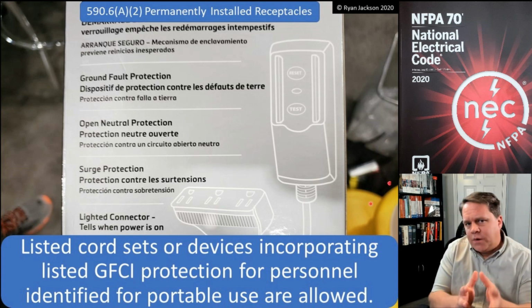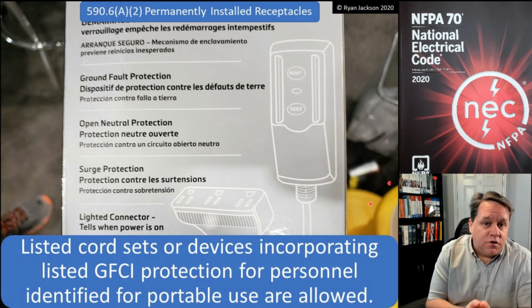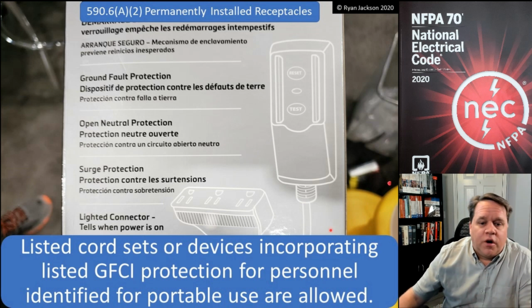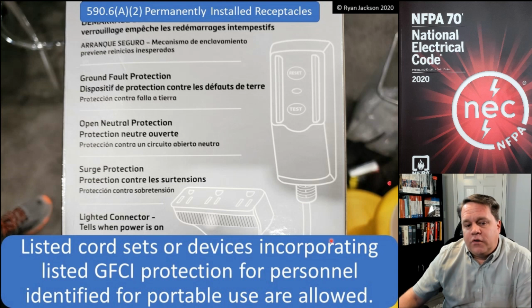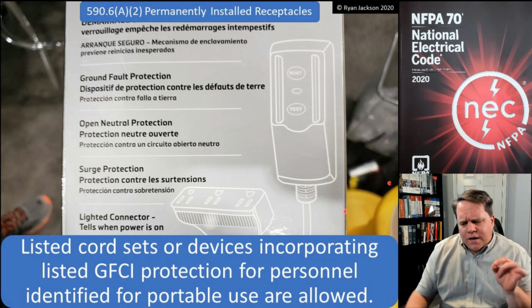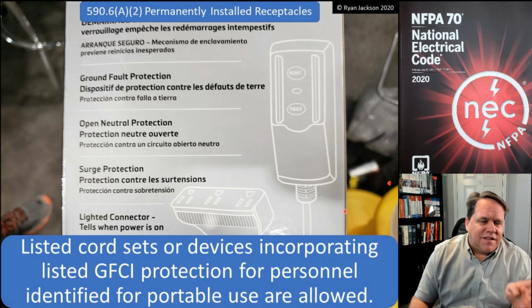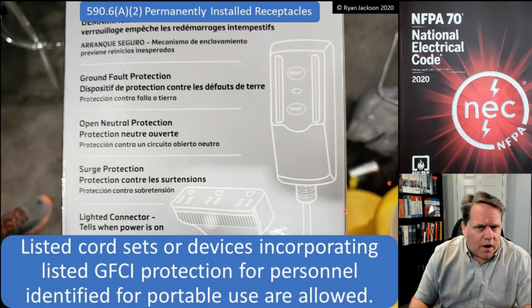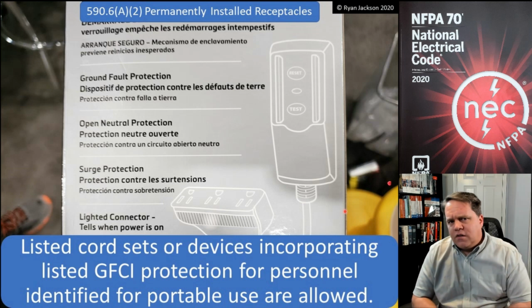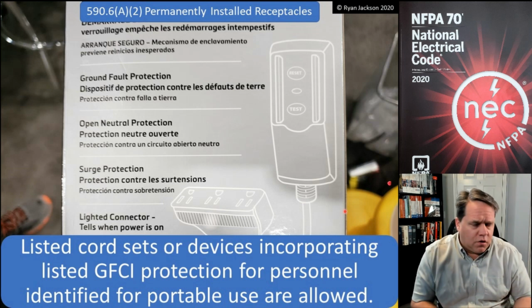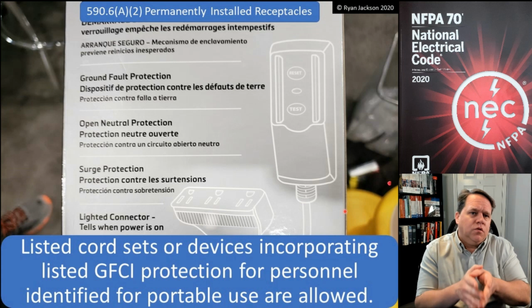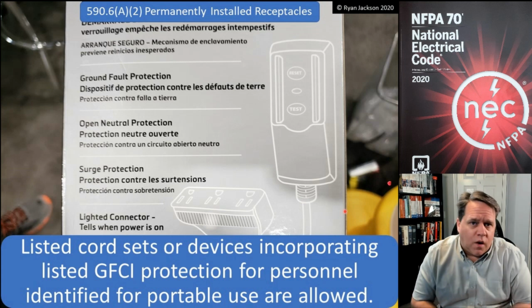Well, it's worded a little bit differently here in A2. It says, listed cord sets or devices incorporating listed GFCI protection for personnel identified for portable use are allowed. It doesn't specify that that's in addition to the required protection. You could read this and easily argue that this can be used in lieu of the required protection.